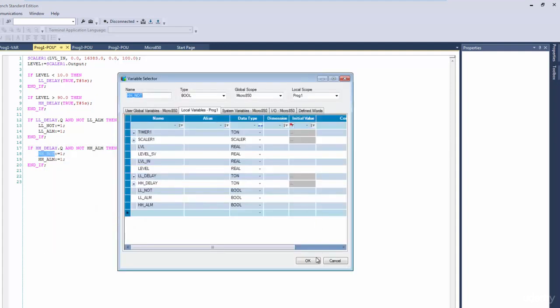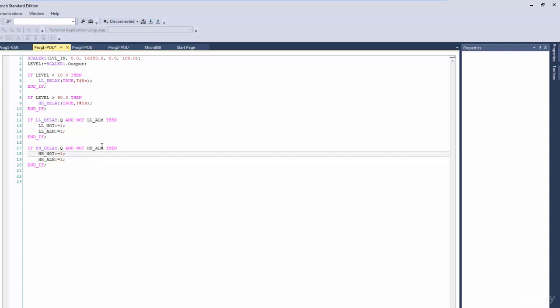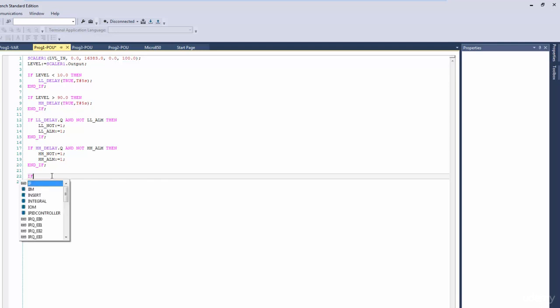The reason that I'm referencing the alarm up here in the if statement and not the notification is maybe somebody has disabled the notification using the alarm silence button, and in that case we want to just look at the alarm. So for that reason, I don't recommend you look at the notification up here, because if you do, it's going to be impossible to silence. Alright, so now we've got our alarm notification and our alarms set. What do we do now? Now we need to figure out a way to get rid of them. So that's going to be using the alarm reset and alarm silence.